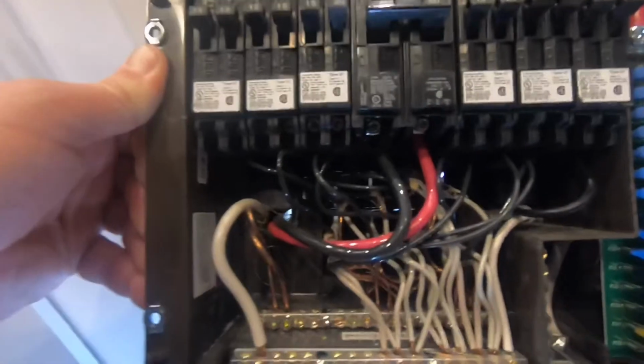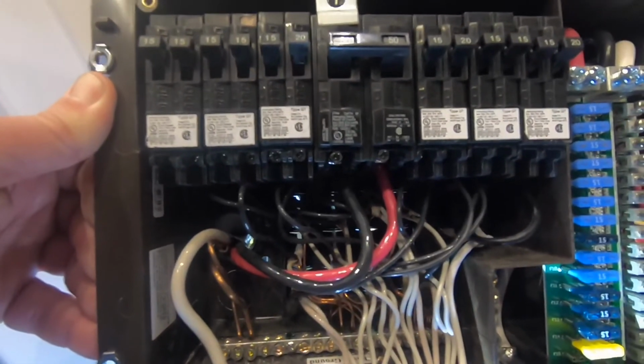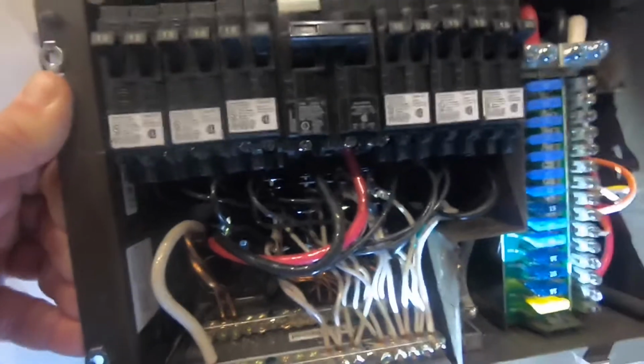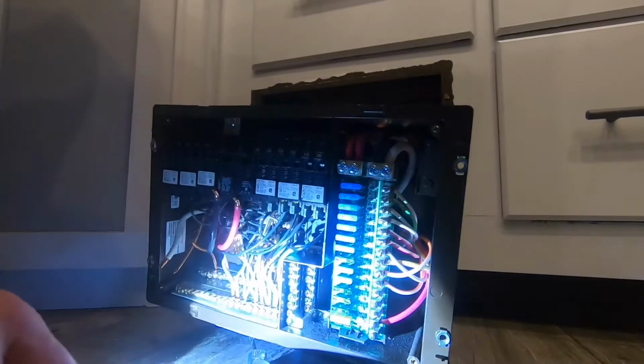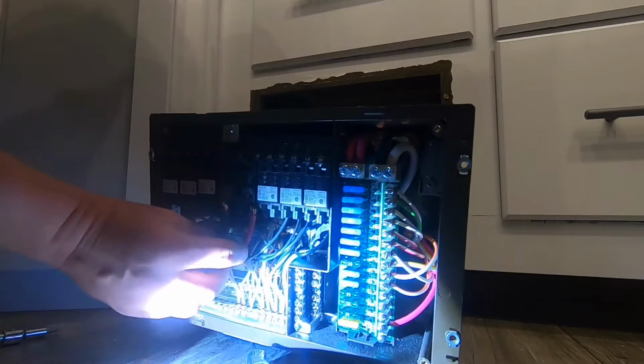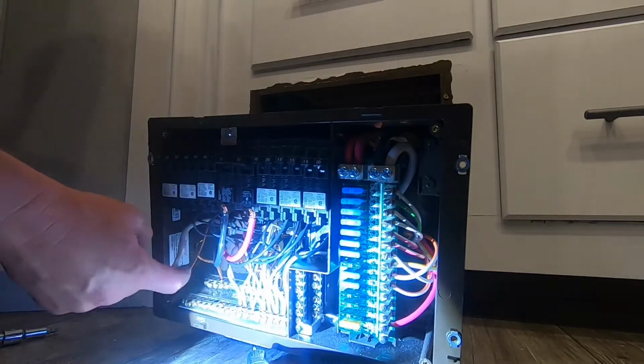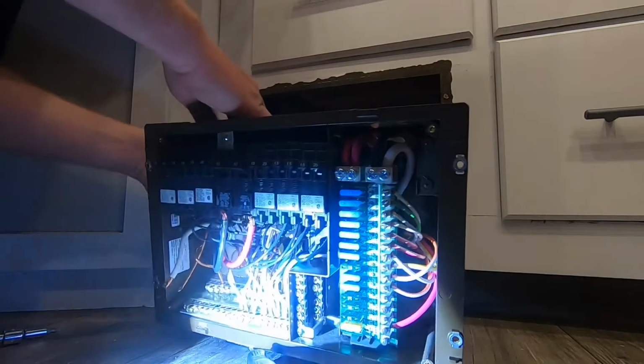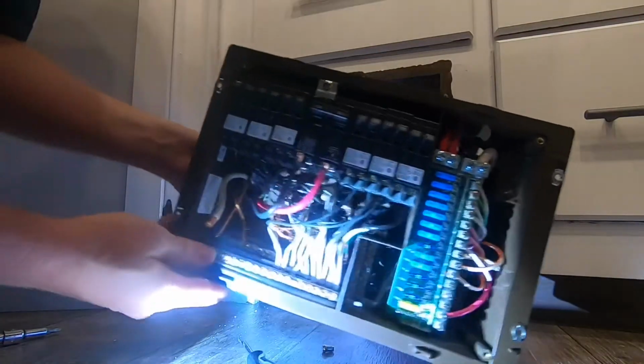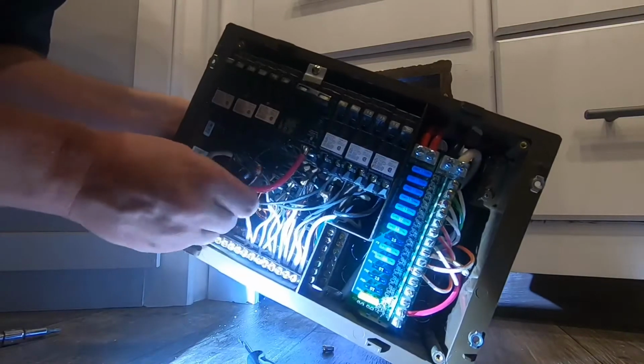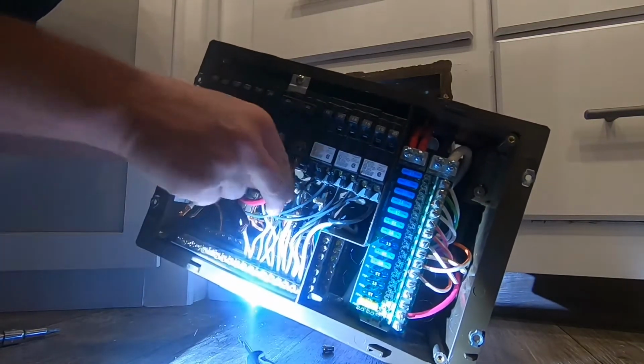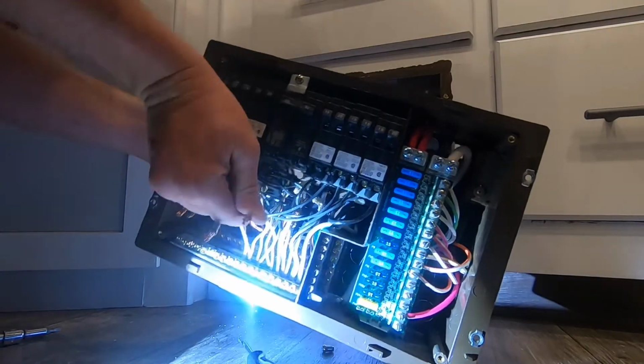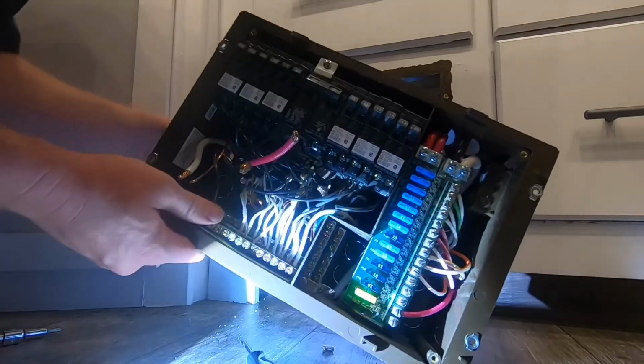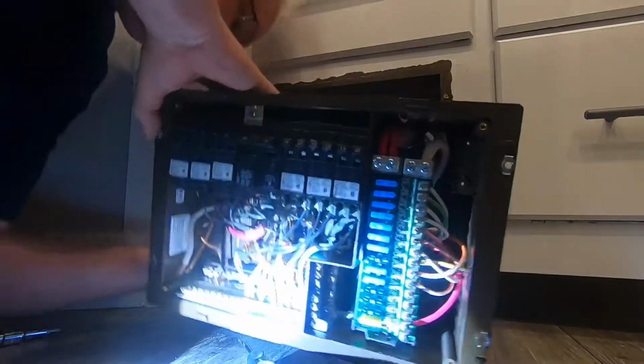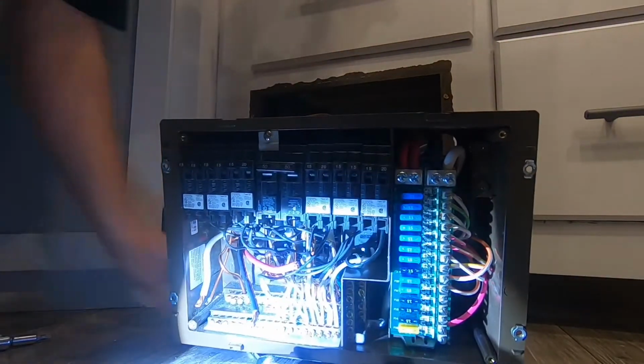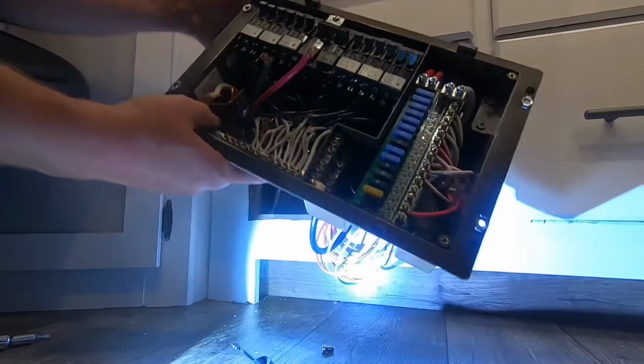Now I'll have to take those power leads out of the 50 amp breakers. Once you get all of this disconnected, you get your ground, lead 1, lead 2, and your neutral. You loosen up the little plate in the back, and you'll pull this main wire back out. If yours is anything like mine, the torque on these was pretty insane, I almost couldn't get it out. Now we'll just back all of this back out through the hole.